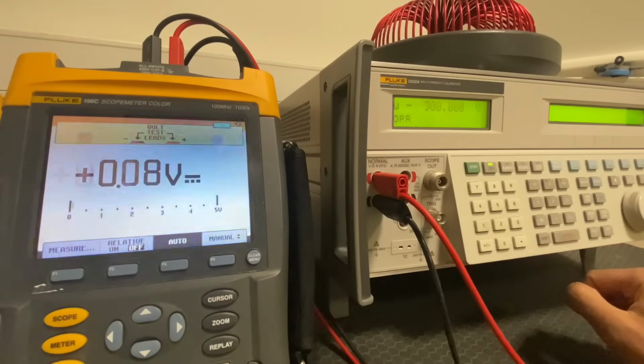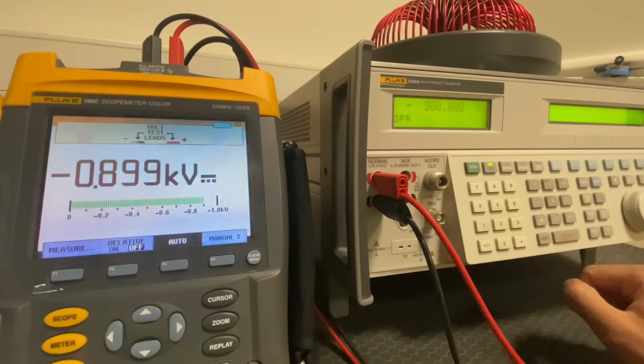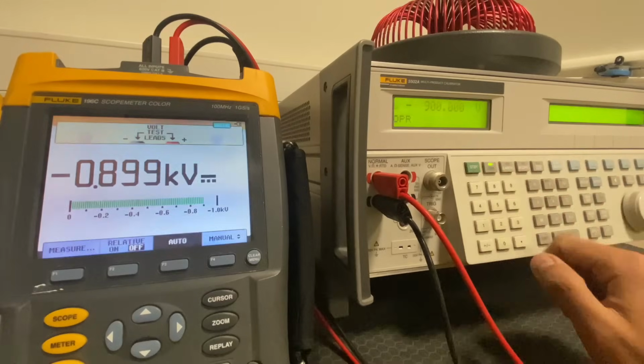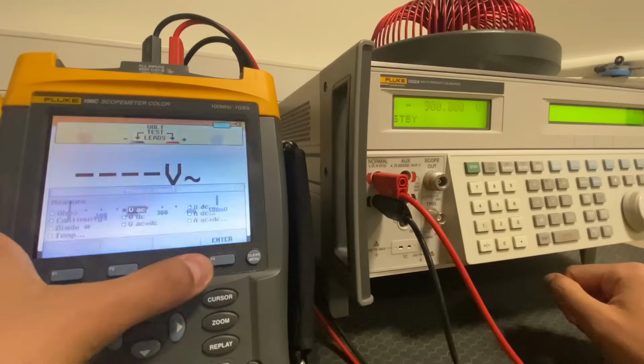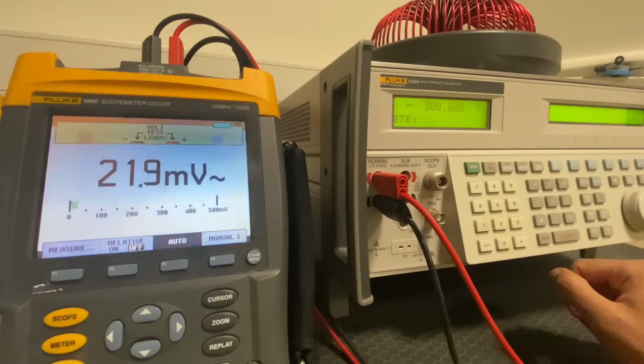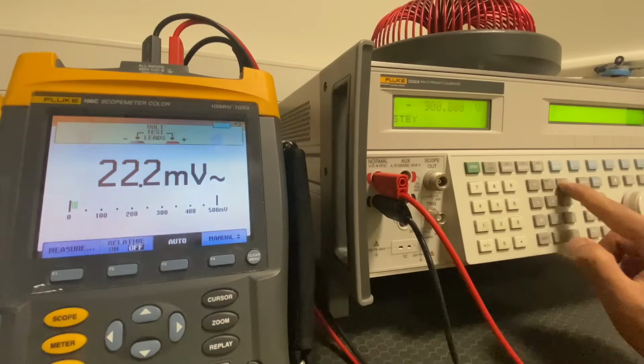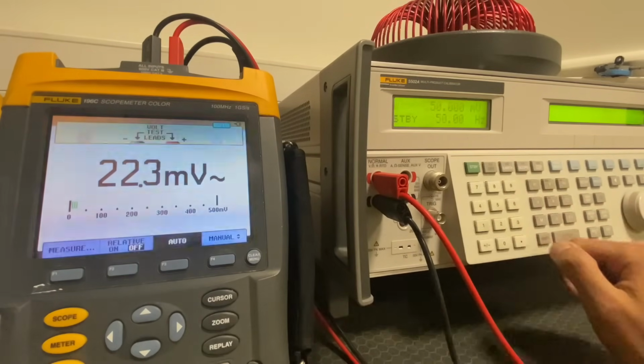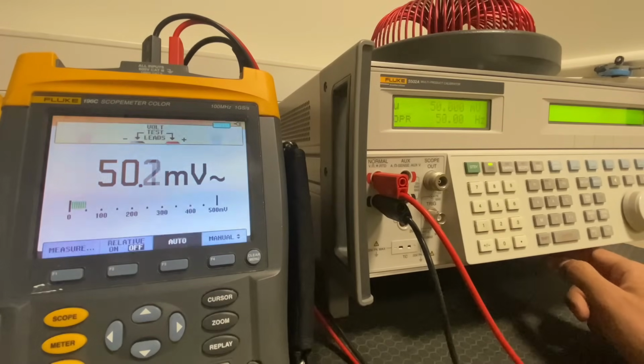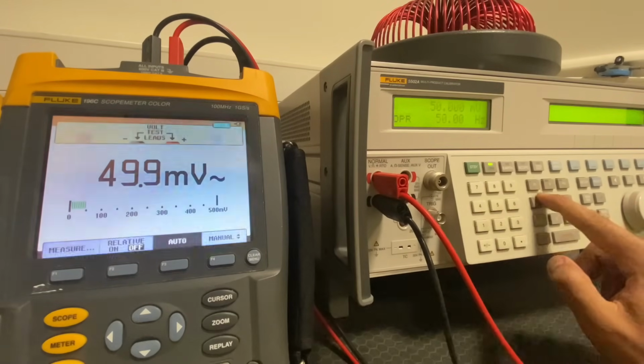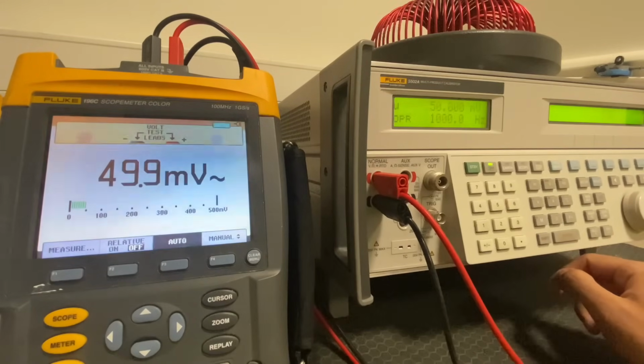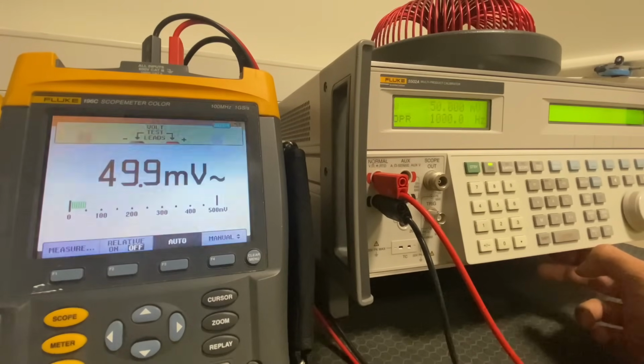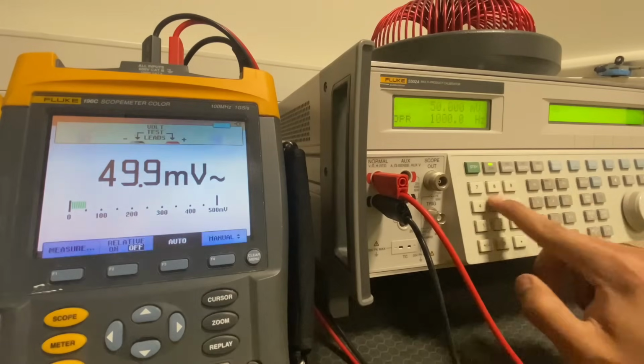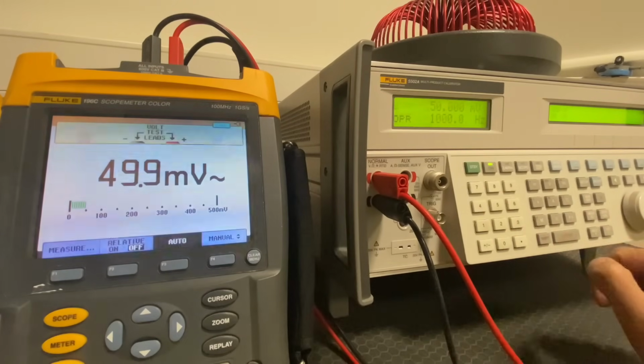Now let's start with the AC voltage measurements. First, we will measure 50 millivolts and 50 Hz in the 500 millivolt range, since frequency is included in AC voltage. We will check with 50 Hz and 1000 Hz to observe the highest fluctuation. 50 millivolts looks good at both frequency values. Now let's continue with 450 millivolts.